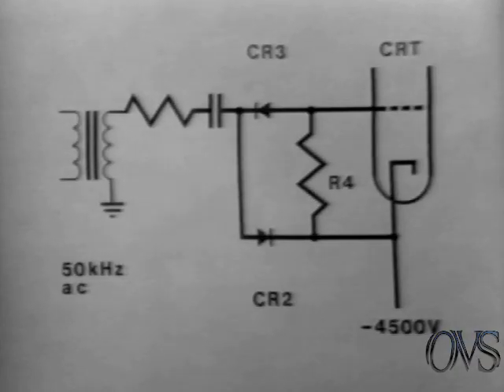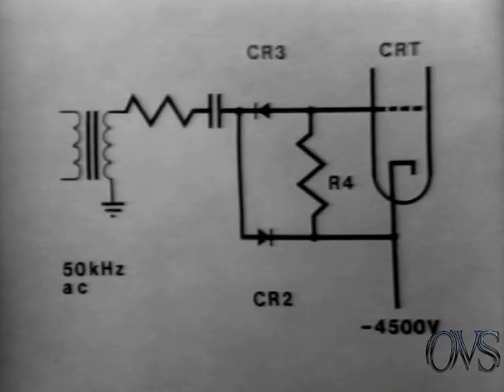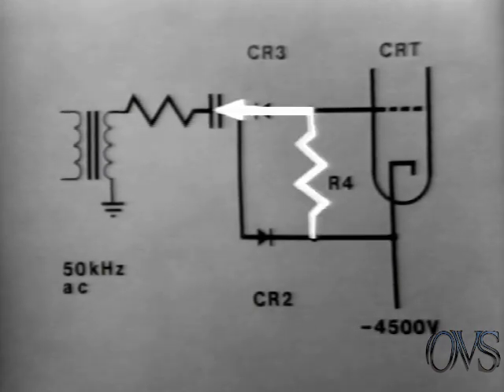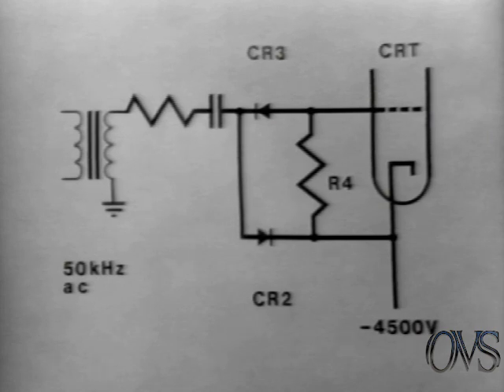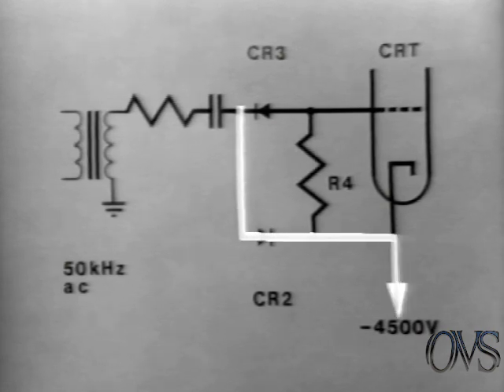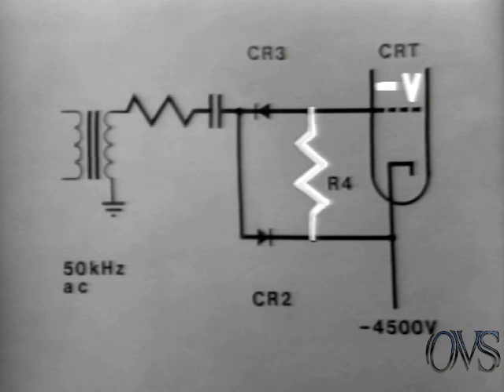Now let's examine the high voltage supply in more detail. The quiescent grid-to-cathode bias is developed across R4, part of a DC restorer circuit. The 50 kHz AC output from the oscillator is transformer coupled through a current limiting resistor and coupling capacitor into the DC restorer. On one half cycle, current flows through CR3 and R4. On the other half cycle, current flows through CR2. The voltage drop developed across R4 provides a negative voltage on the grid of the CRT.